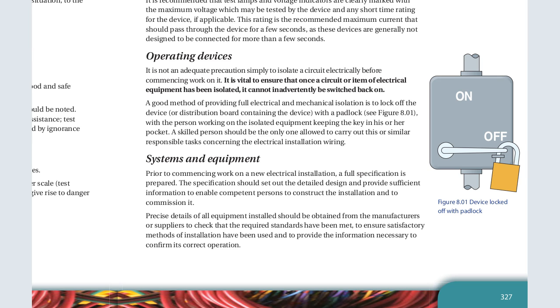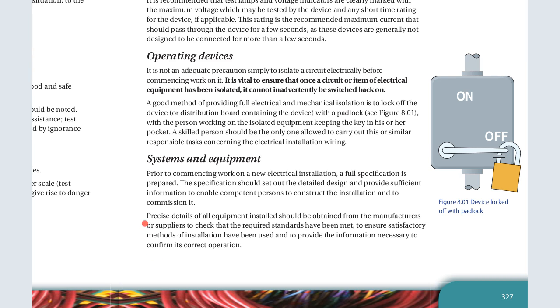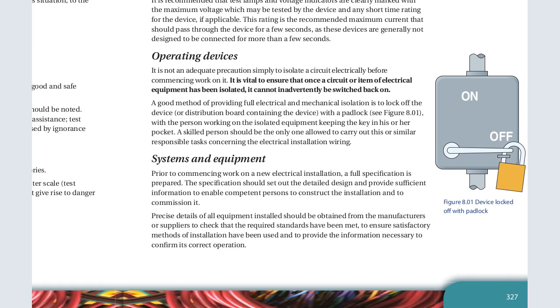So a good method of providing full electrical and mechanical isolation is to lock off. That is what I've already said. The device, that is the distribution board containing the device, is locked off with a padlock, with the person working on the isolated equipment keeping the key in his or her pocket. So a skilled person should be the only one allowed to carry out this or similar responsible tasks concerning the electrical installation wiring.